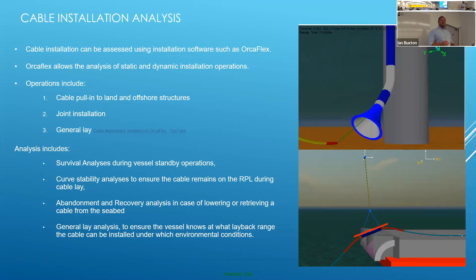So the layback is the distance of the cable from the rear of the vessel to the touchdown point, as I mentioned earlier, and that can really change a lot depending on the water depth. So traditionally at the moment, we're working on fixed bottom wind, which has maybe a depth range of about up to 50, 60 meters. But as we move into the offshore floating wind, it's going to be a very different scenario where we're going to have 100, 150, 200 meter water depths, if not more. So that general lay and the tension the cable's exposed to in offshore floating wind is going to be a lot more significant than it is at the moment with the fixed bottom structures we're working to right now.